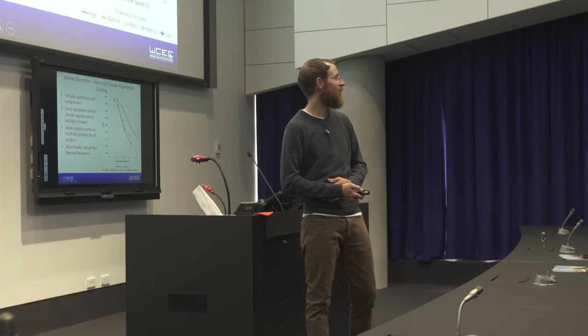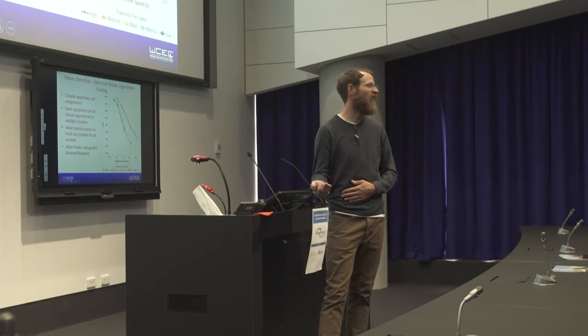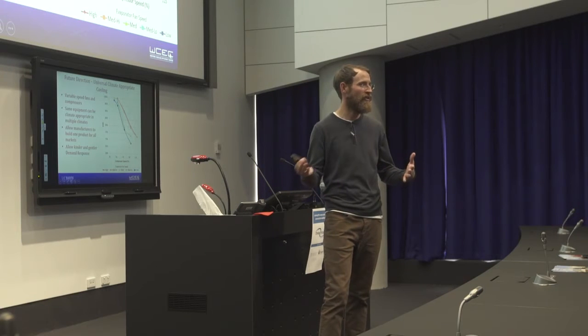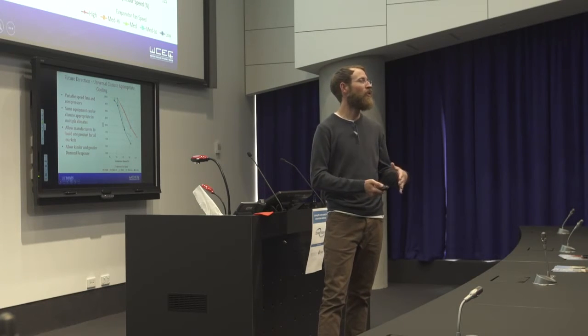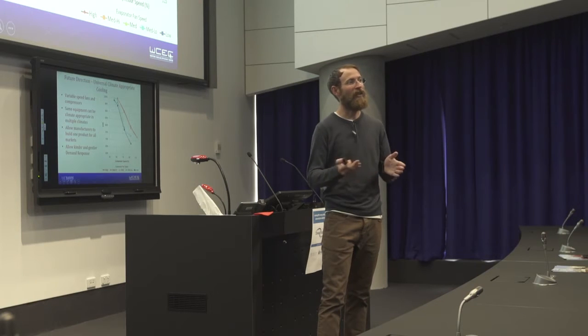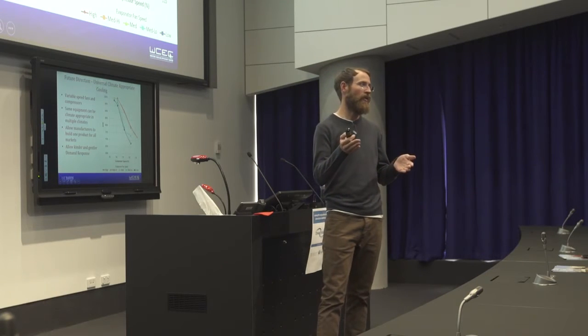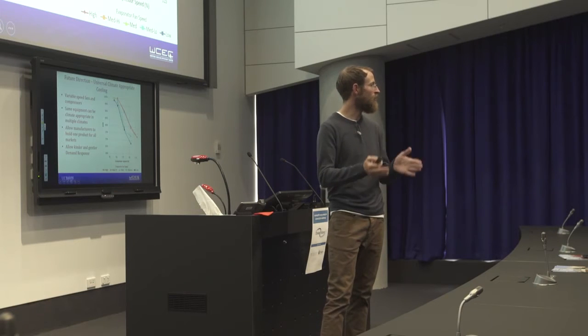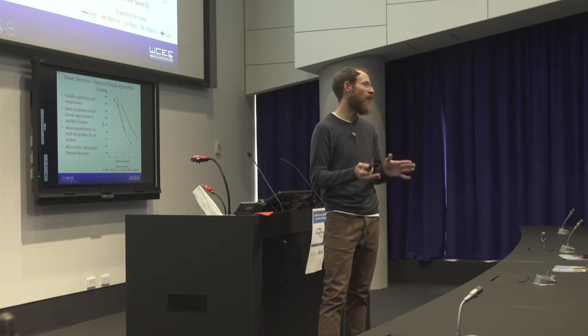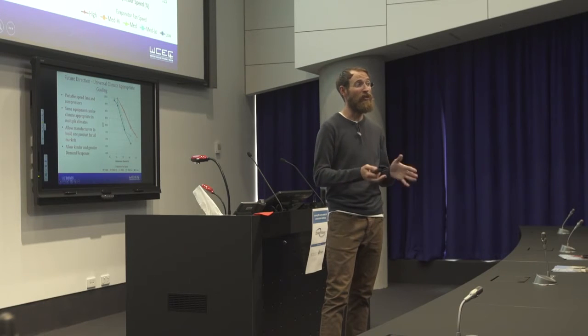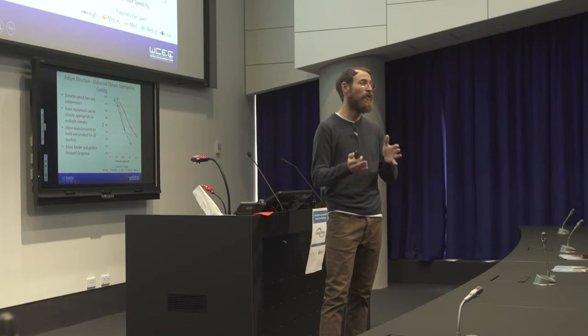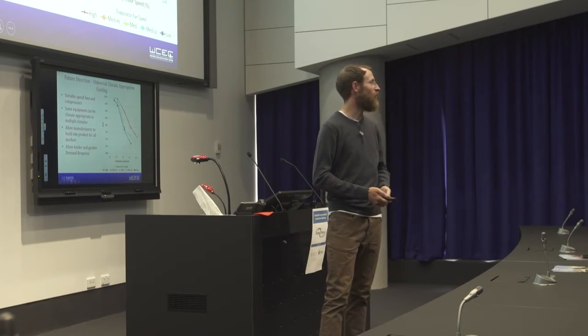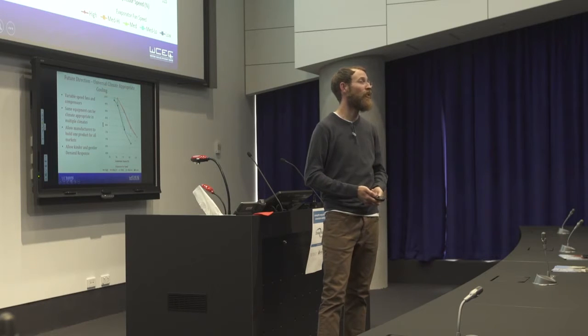And what's really exciting is then if you couple this together with a simple retrofit like an evaporative condenser air pre-cooler, you can reduce the total demand for the system by almost 40%, which is really exciting. If you take a condenser air pre-cooler and you add it on to a single speed, constant volume rooftop air conditioner, you might reduce demand by almost 30%. But if you do that with a variable speed air conditioner and tune everything appropriately, it really boosts your performance without reducing your capacity.